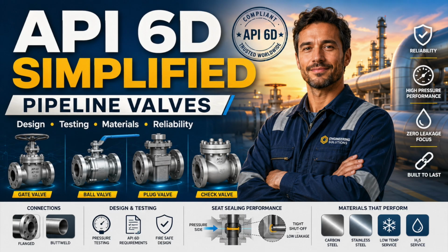The most common valve failures often begin with simple assumptions: assuming every ball valve is bidirectional, assuming full bore means piggable, assuming pressure class proves complete suitability, assuming double block and bleed means the same thing to everyone, assuming metal seats provide zero leakage, assuming factory testing proves lifetime reliability, assuming the actuator will operate the valve under worst-case differential pressure, assuming maintenance access can be solved later, assuming the standard will fill in missing design intent. It will not. The corrective action is not to produce a longer specification filled with copied clauses.